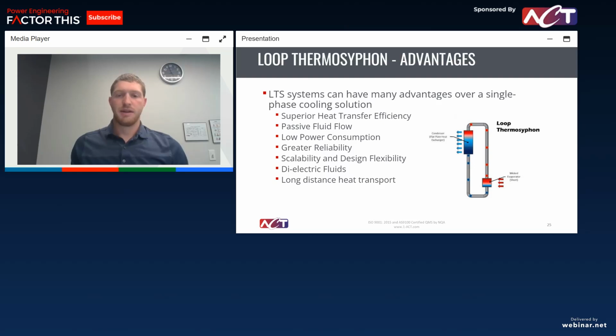Another thing, scalability and design flexibility. I'll get a little more into scalability on the next slide, but in terms of your flexibility, as I talked about, really your evaporator is where your heat generating components are. It's typically a cold plate, but your condenser can be located remotely. So you have a very small footprint where your heat generating components are, which is oftentimes very tightly packed, and there's not a lot of space claimed. So having that flexibility to move your condenser around, as long as you have that gravity, that height difference between the two, gives you a lot of options.